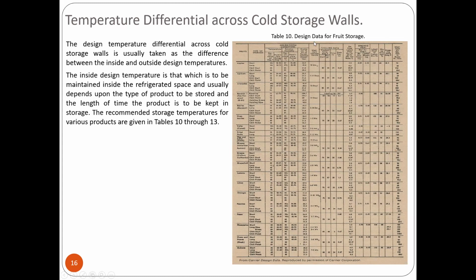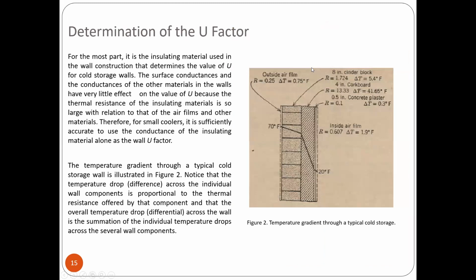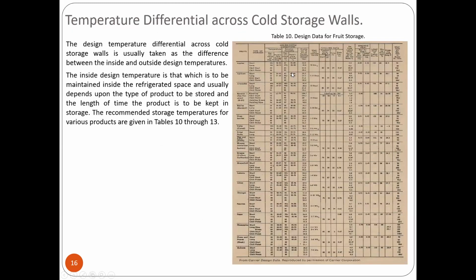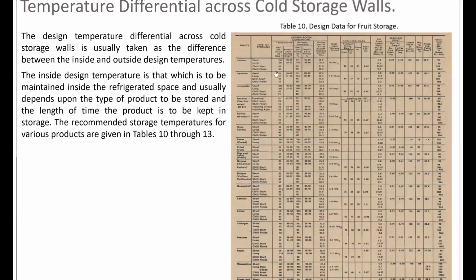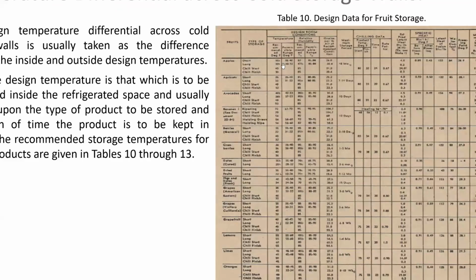Table 10 is design data for fruit storage. Here are apples, apricots, avocados, all types. Type of storage: short, long, chill start, chill finish. These are the recommended temperatures, design room conditions. In Fahrenheit, 35 to 40. Relative humidity also has a recommendation. Apples, moist. Maximum storage period, 8 months perhaps. 7 to 14 days for apricots. That is the maximum storage period. That is why apples are stored for several months before December.